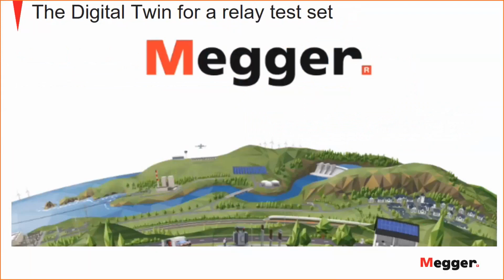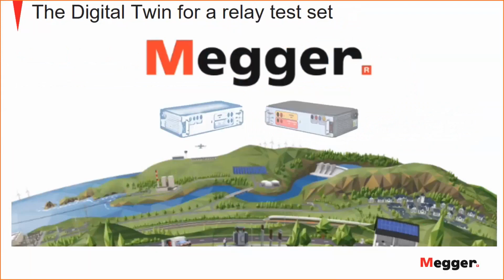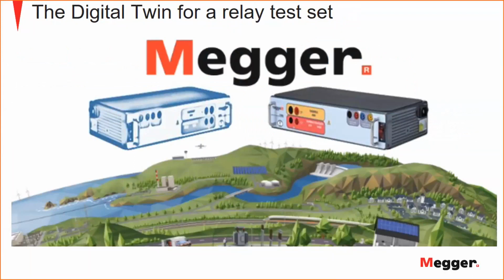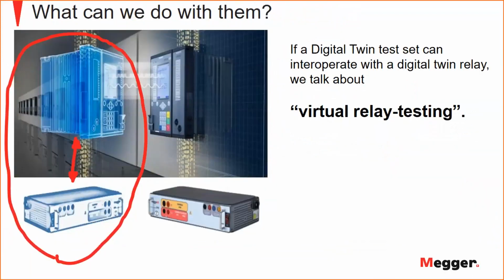Megger, we recently did a digital twin for the relay test set. Now you see only a small one, SMRT1, but we have a digital twin for many other test sets. And it's a digital copy of what the relay test set will do. And now you have to see that it's not really buzzwords.